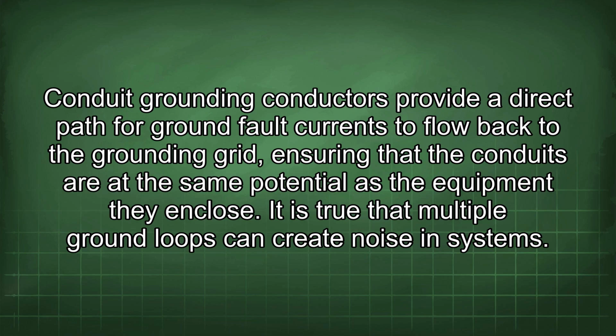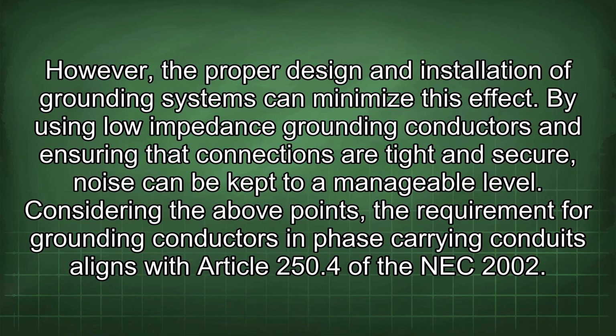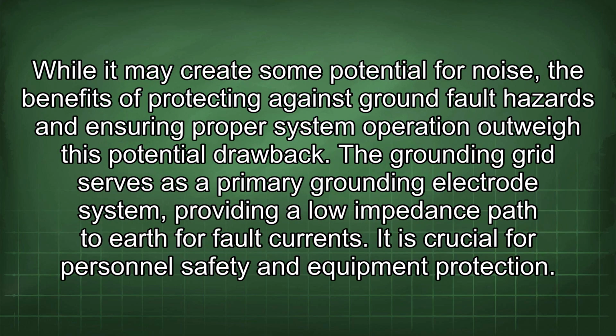It is true that multiple ground loops can create noise in systems. However, the proper design and installation of grounding systems can minimize this effect. By using low-impedance grounding conductors and ensuring that connections are tight and secure, noise can be kept to a manageable level. Considering the above points, the requirement for grounding conductors in phase carrying conduits aligns with Article 250.4 of the NEC 2002. While it may create some potential for noise, the benefits of protecting against ground fault hazards and ensuring proper system operation outweigh this potential drawback.